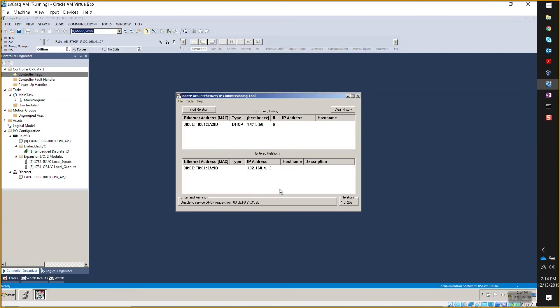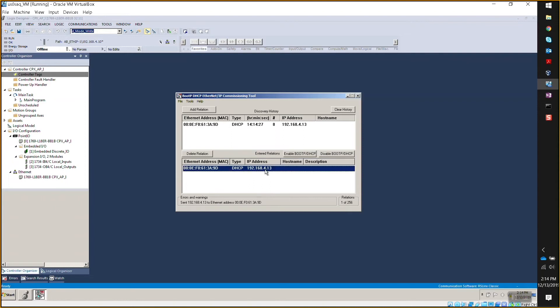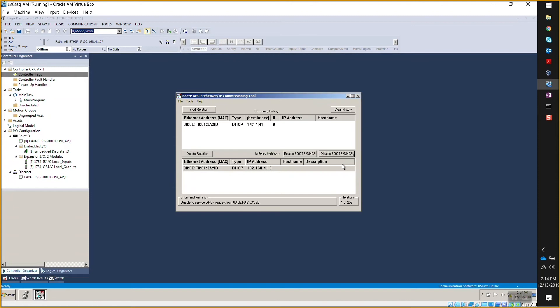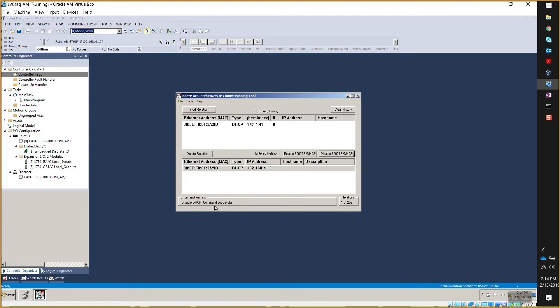All right. And now it comes up in the bottom where it says entered relations. Now I would click on that. And what at this point, what you want to do is to disable the BootP DHCP request. So you see the button on the right says disable it. This one. Yeah. Click that button. And I've seen sometimes I get messages with Rockwell devices that says it's unable to service the device. But hit that button again, and okay. Command successful. There you go. So I think now you've got this device is now set up for that IP address.